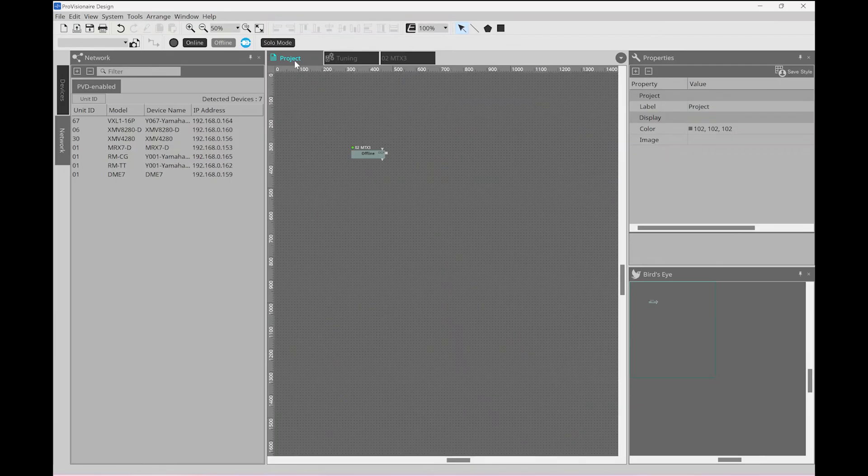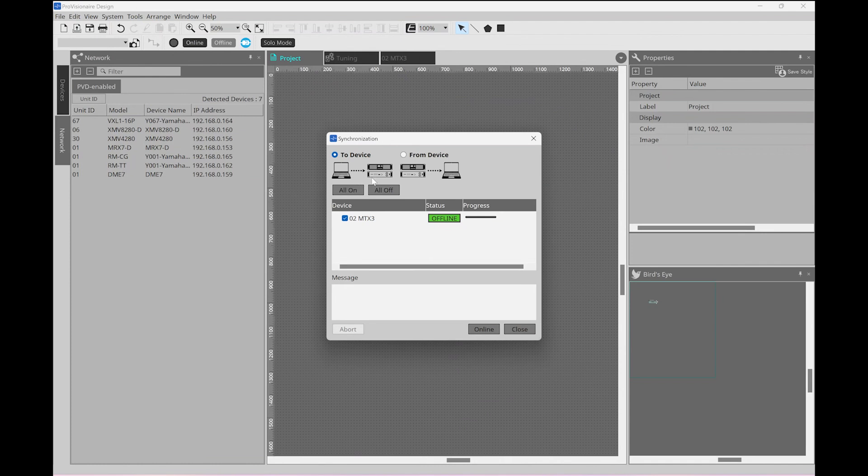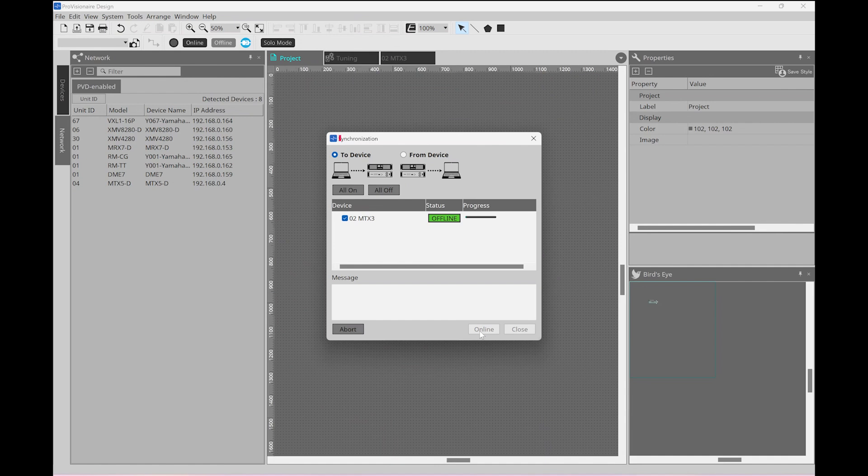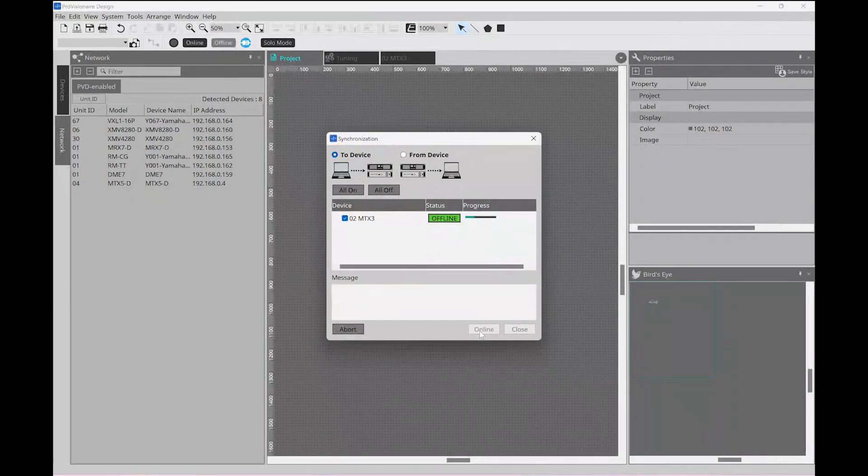Clicking the online button at the top will allow us to connect to the device, so this will synchronize from device to accept its current configuration or to device to push our newly created configuration onto the MTX. Bear in mind, as mentioned before, if the MTX has already got a program on it from the MTX editor software, the only option that will work here is to device. That's to overwrite the current configuration.